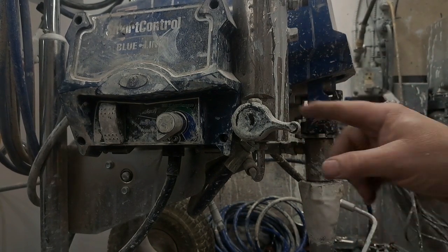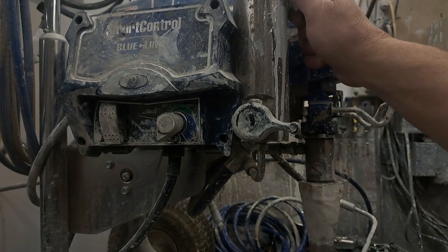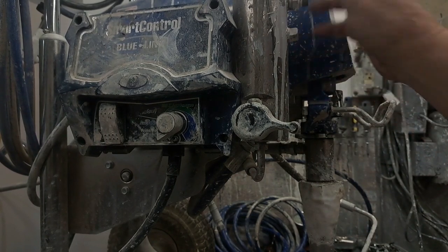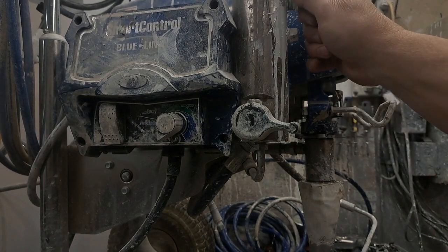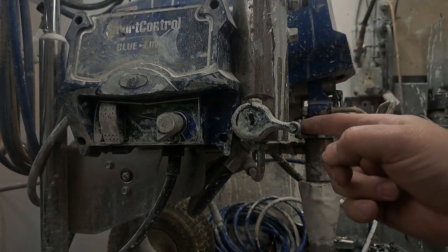Typically the prime valve will blow open, and that, again, is going to be an indicator that your transducer is bad. It could be a computer issue, but 9 times out of 10 it's going to be a transducer. So we're going to look at how to replace that today.